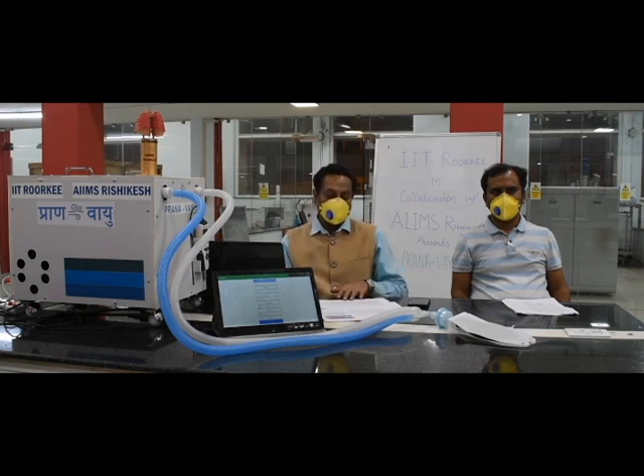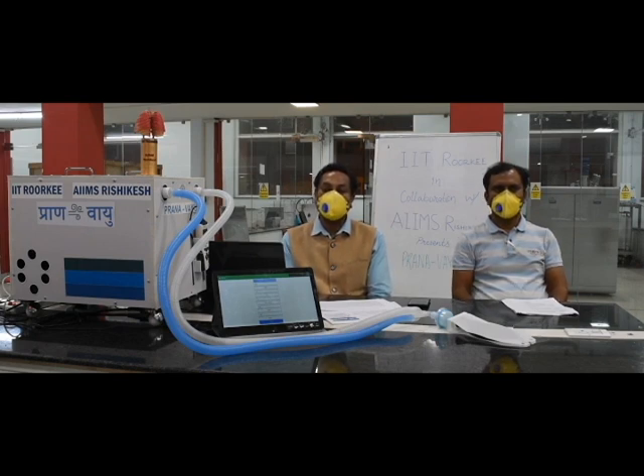When we talk about the hardware part, we had certain constraints. One of the biggest constraints was that this particular ventilator cannot work on compressed air. In corona situation, it is essential that maybe an ICU has to be made in an open field. In an ICU, usually you have a compressed line available. However, in an open field, that particular compressed line is not available. Therefore, we identified that we have to develop a self-sustainable machine which can generate its own flow. Therefore, we decided to use a centrifugal prime mover.